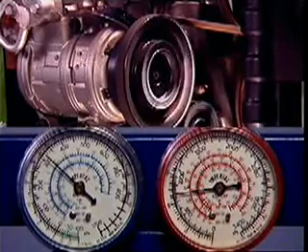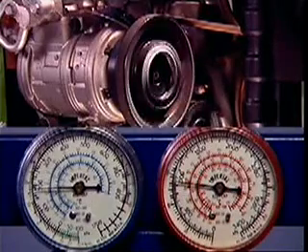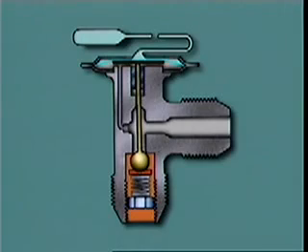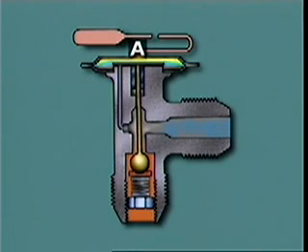When the compressor switches on, the suction from the compressor removes refrigerant vapor from the evaporator and lowers its pressure. This reduces the pressure in chamber B and allows the pressure in chamber A to move the valve away from its seat by the action of the diaphragm.